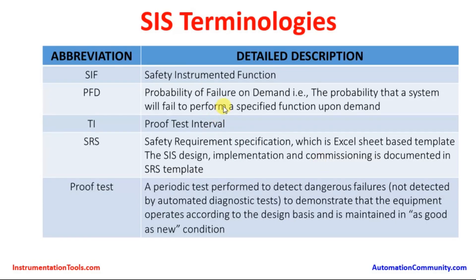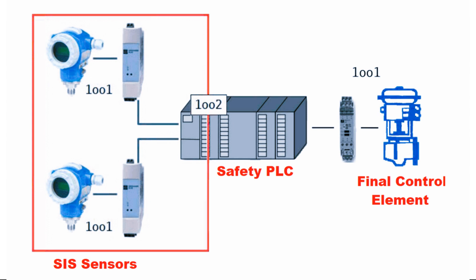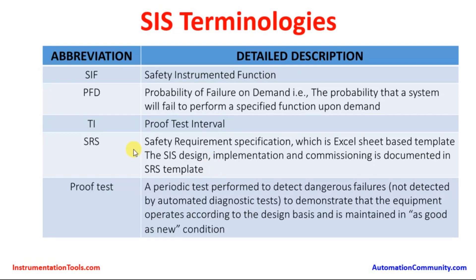SIS — Safety Instrumented System — is the main topic we are discussing and we will be easily understanding this technology. SIF stands for Safety Instrumented Function; the whole function which the SIS is performing is known as the Safety Instrumented Function. PFD stands for Probability of Failure on Demand — that is, the probability that a system will fail to perform a specified function upon demand.